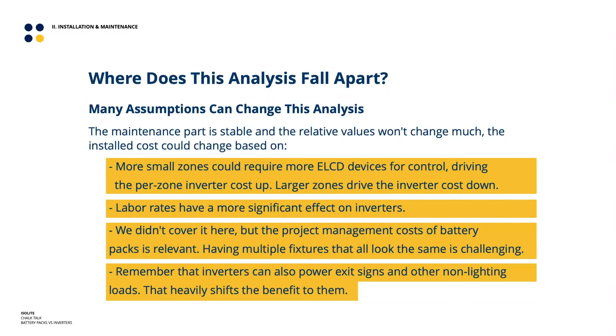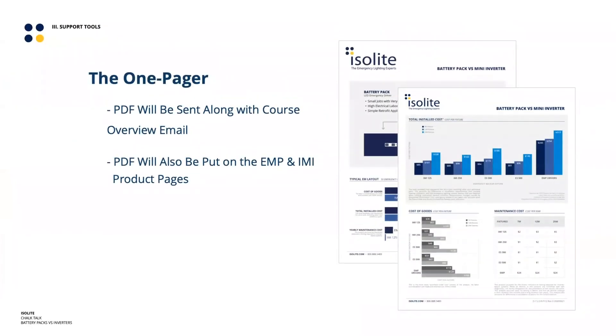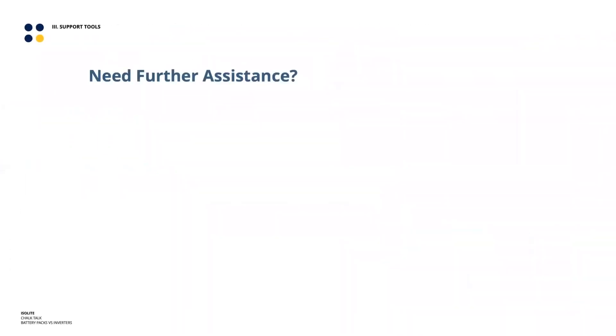The thing that really swings the analysis toward inverters is considering exit signs and potentially non-lighting loads. Since an inverter supplies AC power, if a facility has ventilation requirements for areas of refuge, or you can hang exit signs off the inverter, that heavily shifts the analysis in the inverter's direction. All this information will be presented on a one-pager sent out with this session and posted on the website.